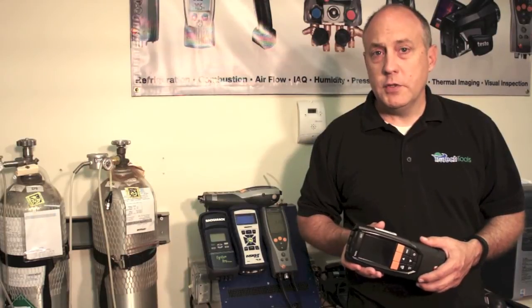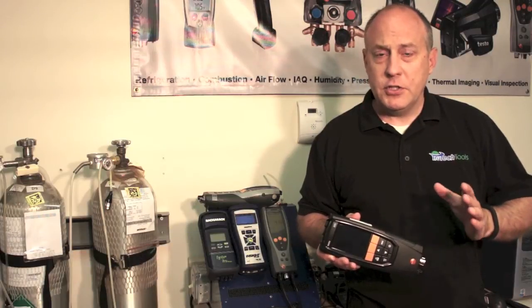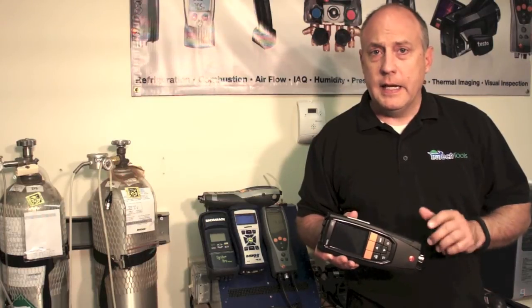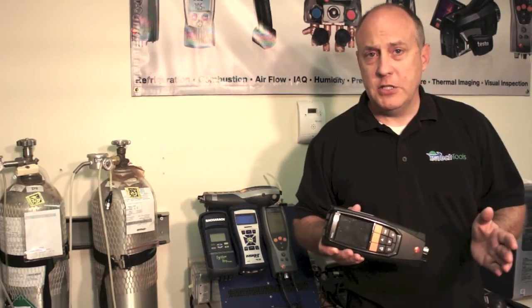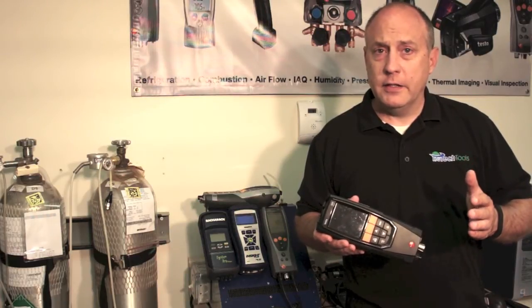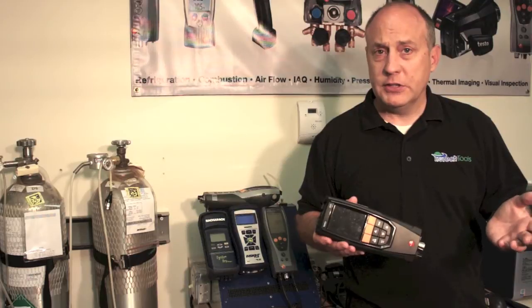One of the best things about dealing with TruTech Tools is we have both a verification and calibration service. Our verification service is a low-cost service that allows you to get your analyzer put on test gas and make sure that it's not leaking and that it's reading accurately. Analyzers should be verified yearly, but only need to be calibrated periodically — perhaps only one or two times in the entire life of the analyzer cells.